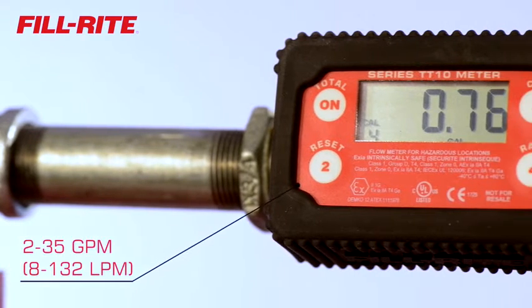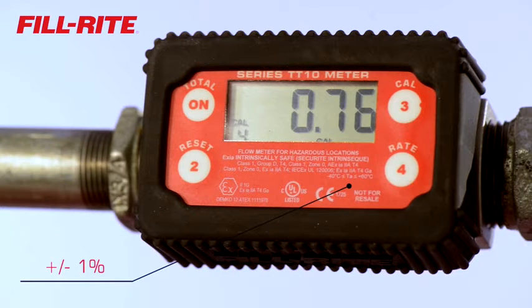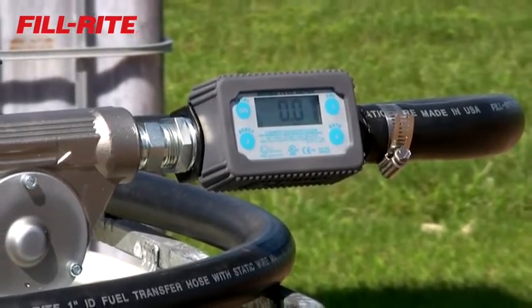The Fill-Rite inline meter operates at flow rates from 2 to 35 gallons per minute, with an accuracy of plus or minus 1%. It also has a permanent memory, so you never lose your totals, even while changing batteries.